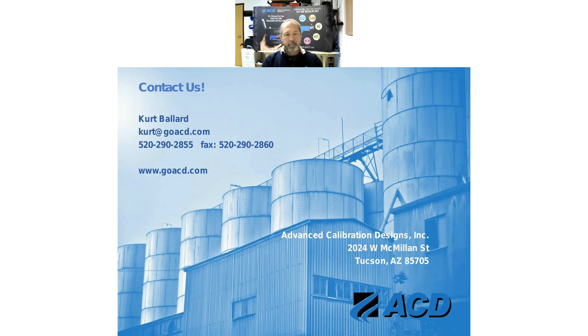Dr. C again. Sometimes when we use the ACD gas generator with a sample draw instrument, for example safety H2S or chlorine instruments, the calibrator does not work and switches off. Can you enlighten us how to use the ACD calibration in such cases, with the sample draw instrument? Yeah, I think what's happening here is he sets his instrument and his calibrator to, say, some flow rate, 0.5 liter a minute, 5 ppm chlorine. Then he hooks it up to his sample draw unit, and that unit is pulling a sample at a different rate. Let's say it's 0.2 or it's 0.8.